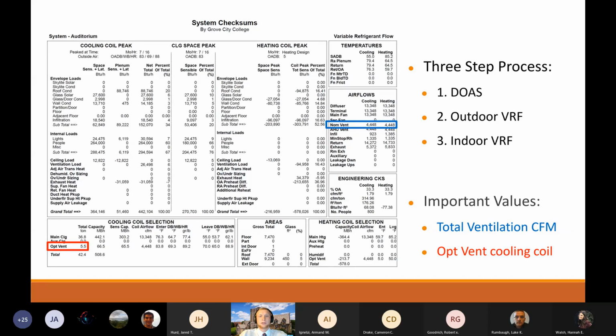So this is an example of what the system checksums report looks like. This is the report for the auditorium. There's 3 main steps in using the numbers from this checksums report to select the equipment that we needed. So first, we had to size the dedicated outdoor air system, or DOAS for short. This is the separate unit that would provide ventilation to the building. So the way that we sized the DOAS was by looking at the total ventilation airflow measured in cubic feet per minute, or CFM. And that's in the blue square. And then the optimal ventilation cooling load is also looked at, and that's in the red square. So you can see there's a lot of different information on this sheet, but we were really just focused on those 2 numbers for making our selections.